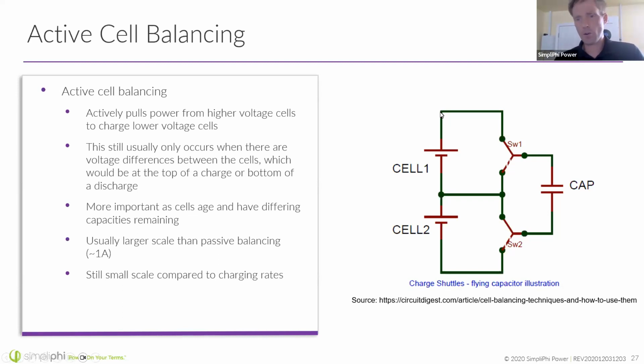If I'm passing a current down through cell number 1 and to cell number 2, and cell number 2 happens to have a lower voltage than cell number 1, what I could do is use these charge shuttles by flipping these active switches back and forth. When that switch is in the top position, it can charge this capacitor. And so if the 2 switches, switch 1 and 2, are both in the top position, the voltage of the capacitor would match the voltage of cell number 1.